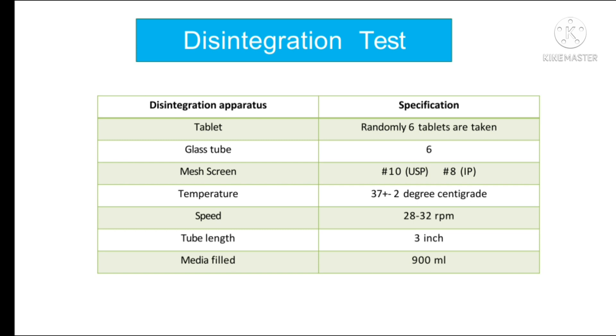The apparatus consists of a basket rack assembly, a one liter beaker, a thermostatic arrangement for heating the fluid, and a mechanical device for raising and lowering the basket in the immersion fluid at a constant frequency rate.